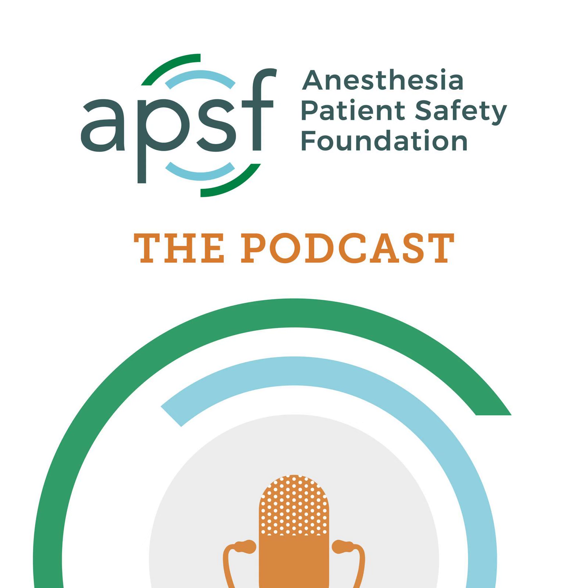The magnet mode was originally developed to enable device interrogation and battery life outside of the operating room. When a magnet is placed over a pacemaker, the response can be programmed by the device team. So this is actually a good question to ask the device team during a preoperative interrogation. What will happen if I place a magnet over the pacemaker?